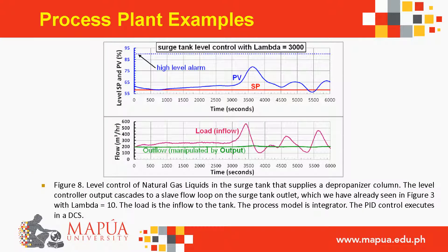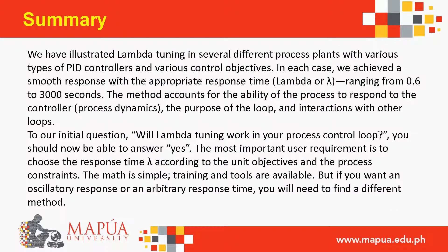Level control of natural gas liquids in the surge tank supplying a depropanizer column: the level controller output cascades to a slave flow loop on the surge tank outlet with lambda = 10. The load is the inflow to the tank. The process model is integrator; the PID control executes in a DCS.